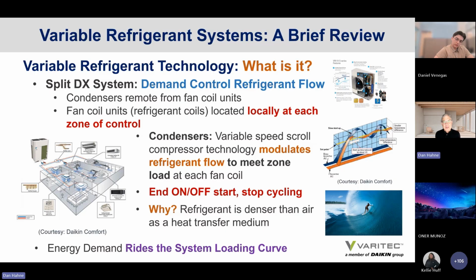What is its technology? Just as a quick review, because we have many different people from various experience levels with HVAC systems in this presentation. Consider variable refrigerant as a demand control refrigerant flow system. Condensers are remote from fan coil units, unlike your package DX units at home. Fan coil units are located locally at each zone of control, and the condensers modulate refrigerant flow based on demand in each or all of the zones.